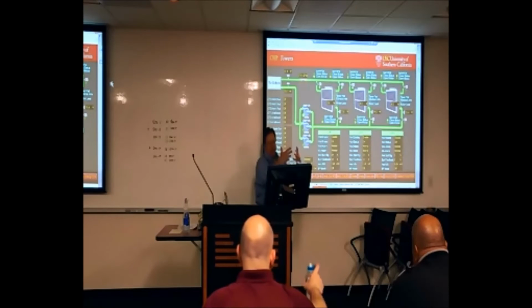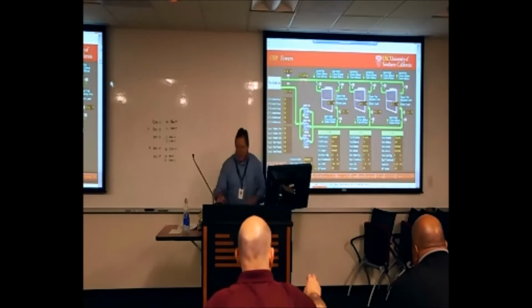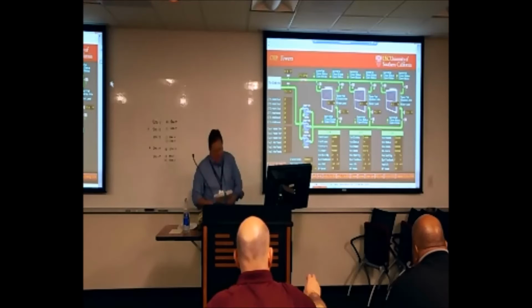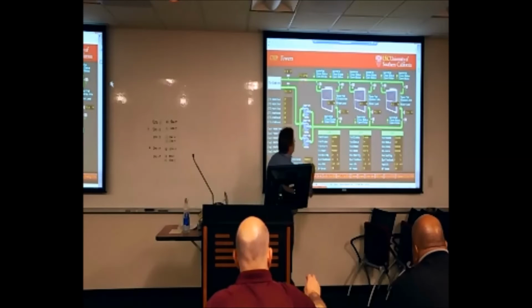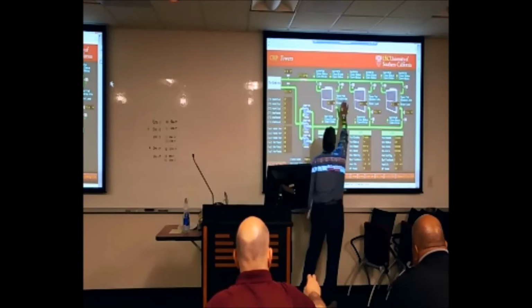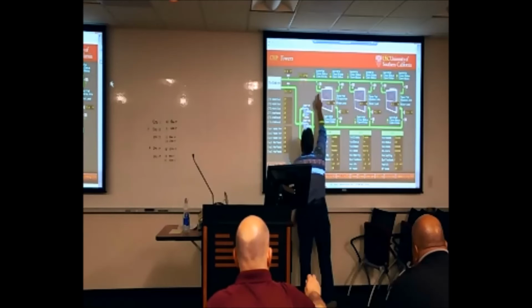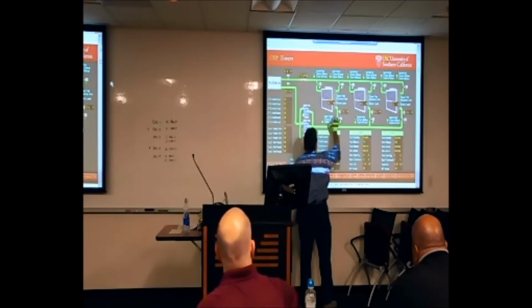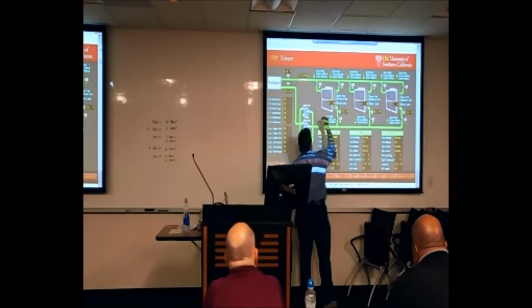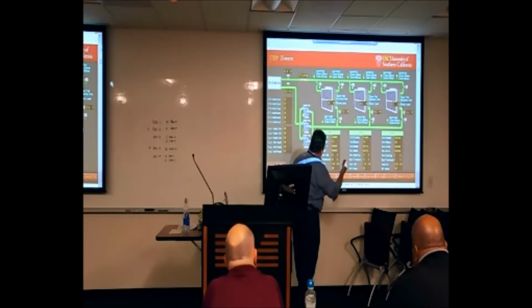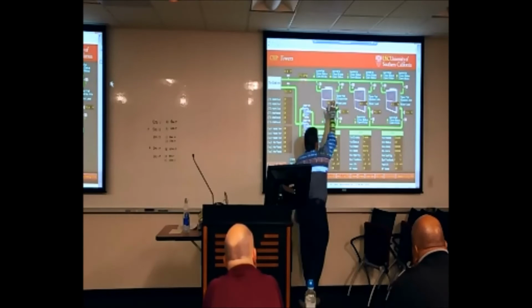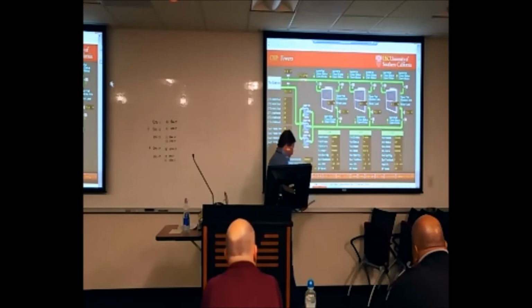And then if you clear it, the tower goes back in operation and runs for another couple of hours, and then it fails again. So we went into what the whole alarm sequence is all about. But what we've currently got programmed is to fail a cooling tower. To get the cooling tower fail alarm, we need to get a valve failure alarm on each one of these valves. So if a valve is commanded open or commanded close and we have a status mismatch, we're going to fail that valve, and that in turn is going to fail the tower.